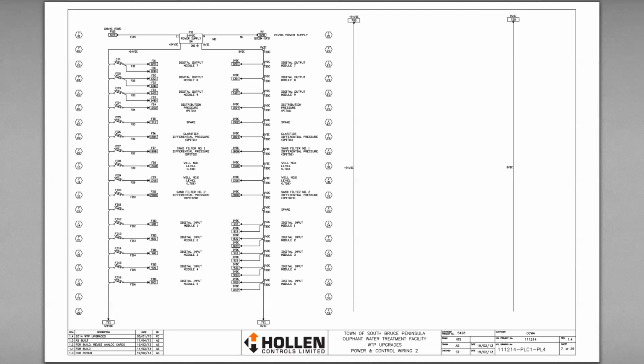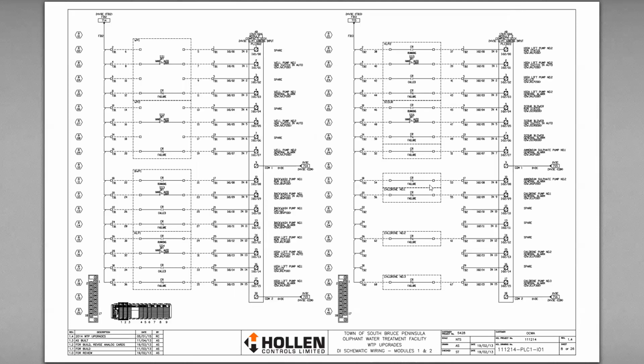So when you're reviewing drawings, especially as the designer or the constructor specifying and putting in equipment, you want to make sure you're putting in adequate protection for it. But you also need to make sure that this power supply is large enough and has the proper output, using the power calculations, to provide power to all the devices downstream of it. You can see here all the different fuses, FD1. Again, we had FU1 for the UPS, and FD1 here for the DC devices. And then we've got our output modules, some pressure transmitters, level transmitters, and the DO cards.